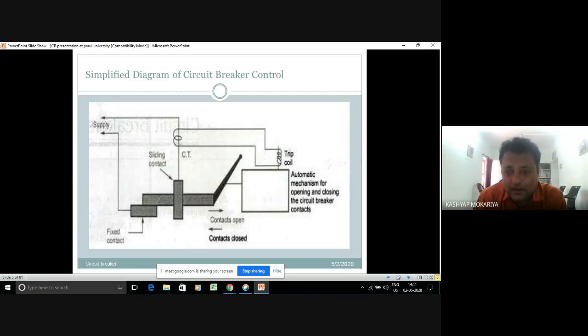Now consider the other load setting. In another load, it is a different setting. But the thing is that all the contacts in an industrial control circuit will be kept in parallel, and if one of the normally open contacts gets closed, it will directly operate your trip coil while this DC supply is on. So now you can visualize this diagram.